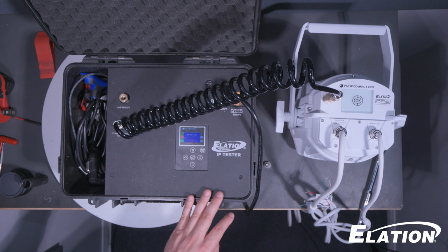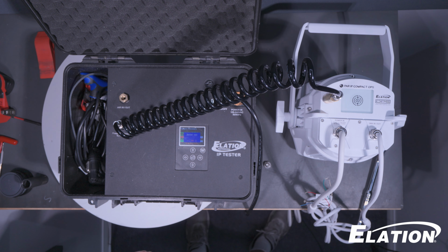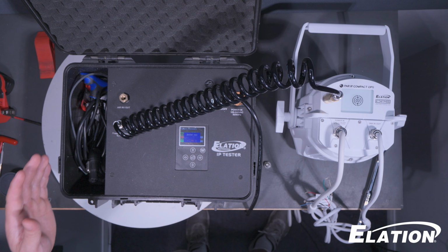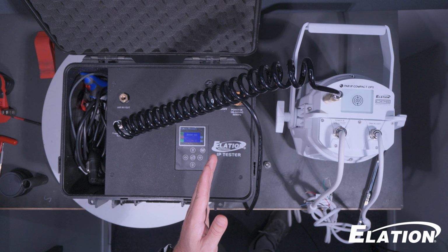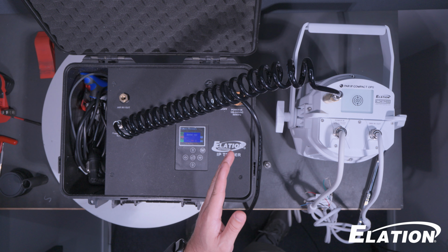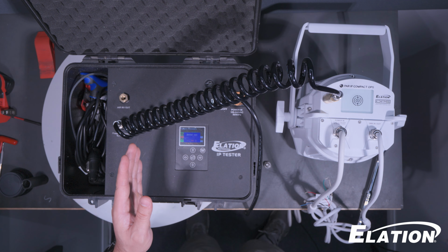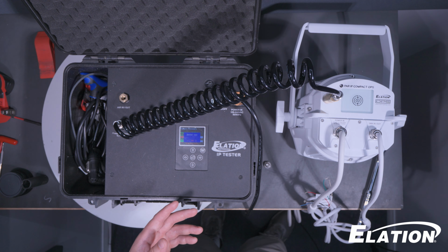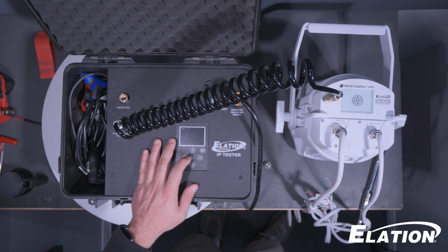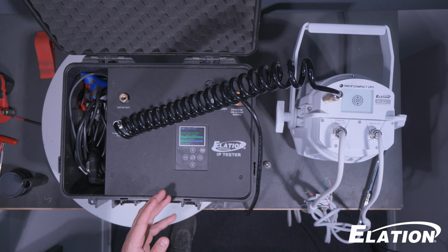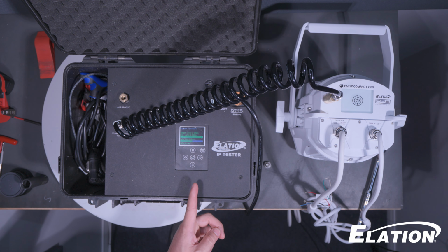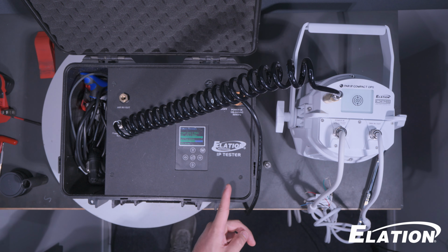So when you run the IP tester to the unit, it's a possibility that it could fail the first time. You could see the loading bar pressurize, and then once it gets to its max, there's a big step off. And so because of the big step off, it might cause the unit to fail. What you could do to really check is to run another test. So you could see on the second test, the loading bar was already kind of more than halfway, and then it pushed it to the full.